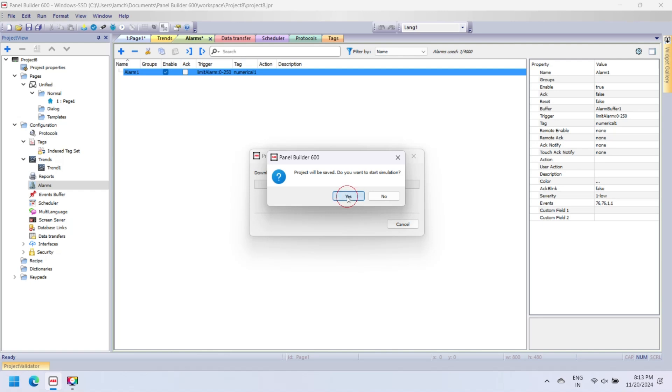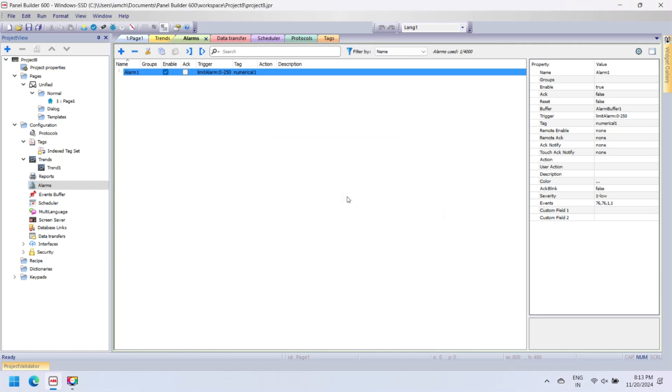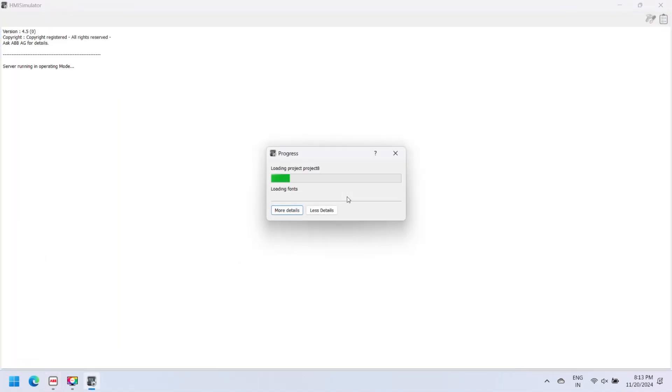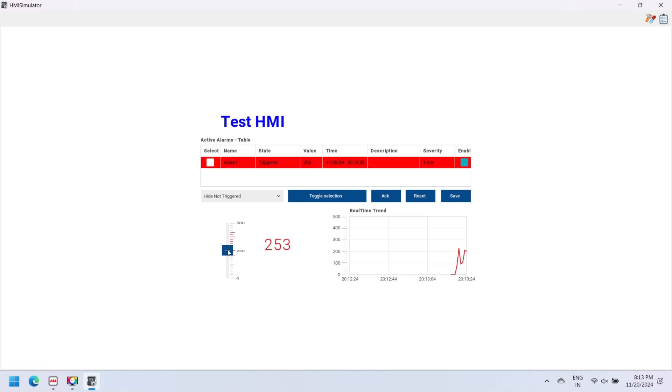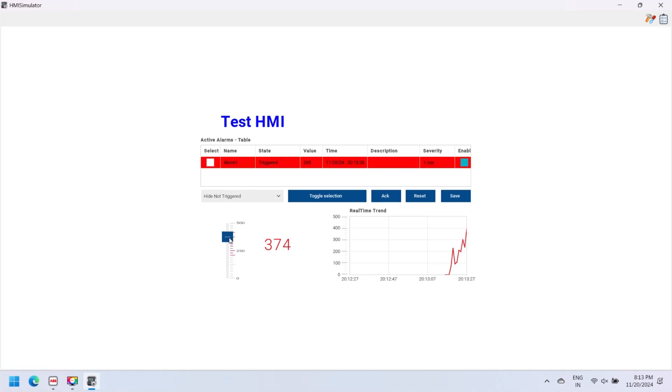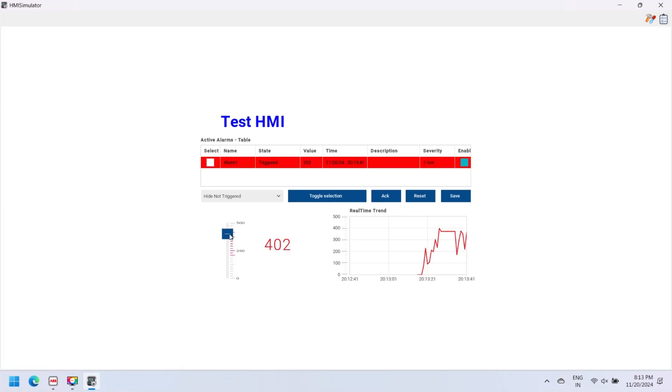Simulation helps to test the HMI screen at runtime. We also simulate alarm and trend conditions. When the value of a variable is changed and the alarm trigger condition is met, the alarm generates a message in the alarm table component. For example, if a numerical value entered exceeds the maximum limit, then an error alarm is triggered. The real-time trend widget can be used to display the changes in value of a tag. Data is not stored in a trend buffer and cannot be retrieved for later analysis.